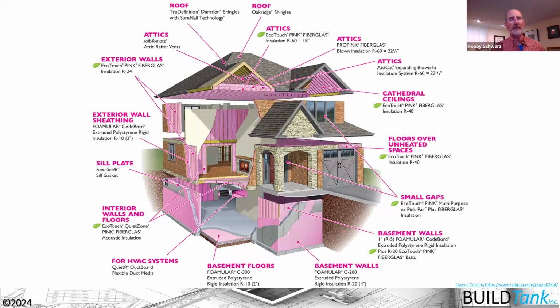So ultimately, with the Manual J, we're looking at all of the building components there. And it goes back to the building thermal envelope. So clearly defining the building thermal envelope. And as the code says, the building thermal envelope creates that boundary condition that separates conditioned space from unconditioned space. So that Manual J is looking at all of these different components, and we're putting the square footage of those components, the R value of those components into the software.